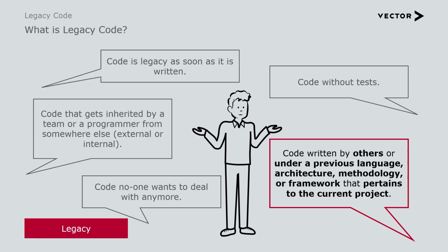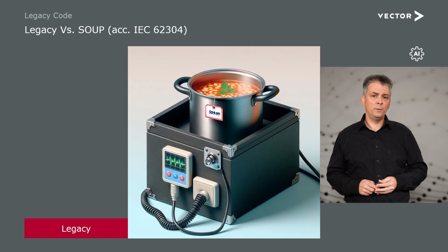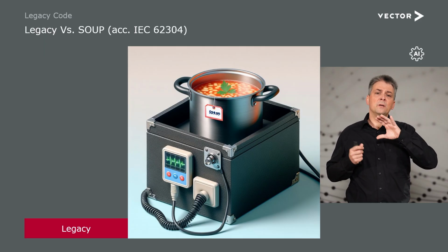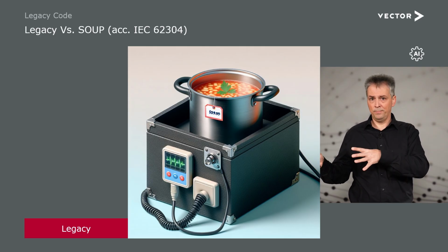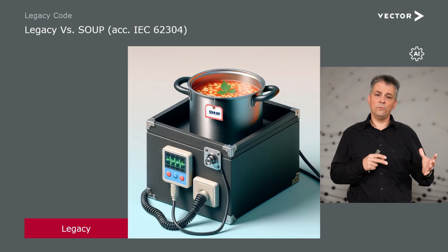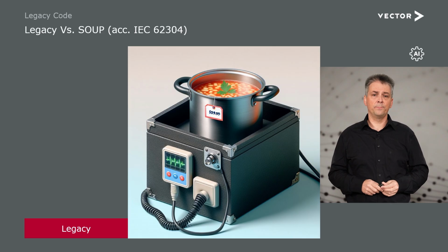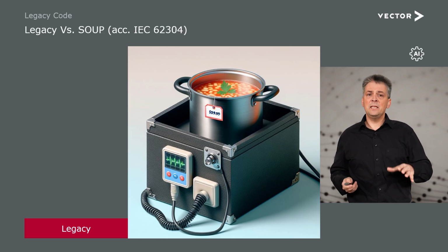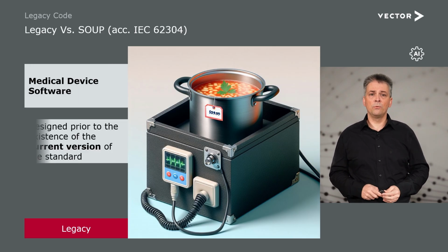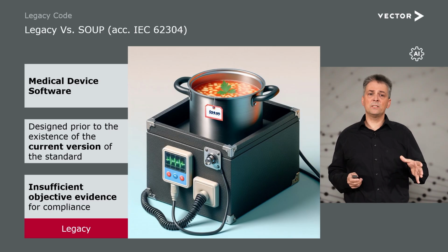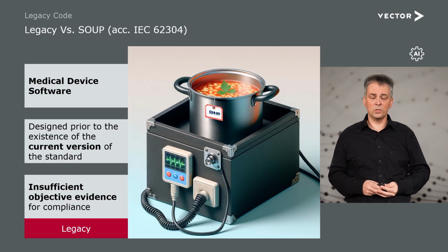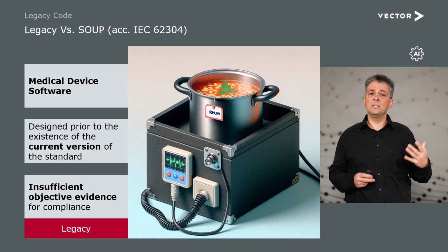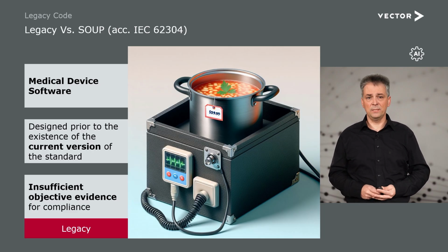Now, in the context of the IEC 62304, we have to separate the term legacy from the term SOUP, S-O-U-P, software of unknown provenance. Legacy in terms of the IEC 62304 is medical device software that was designed prior to the existence of the current version of the standard and that has insufficient objective evidence for compliance.